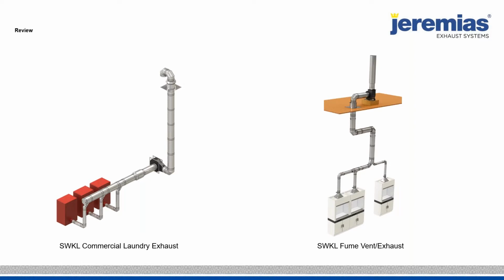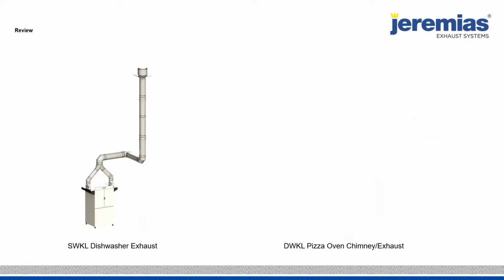Fume hood exhaust. Engineers, once you start looking at the 444 stainless, you're going to recognize that this is better than 316 on sulfuric acid applications. So we're seeing a lot of no weld fume hood exhaust venting out there in the marketplace. But I didn't mention dishwasher exhaust. Every time you have a kitchen exhaust system, contractors like the pop together system on the dishwasher exhaust as well.